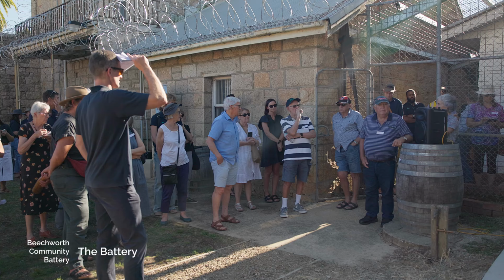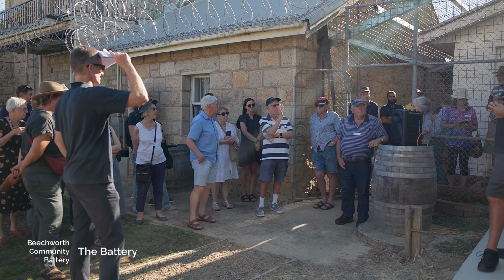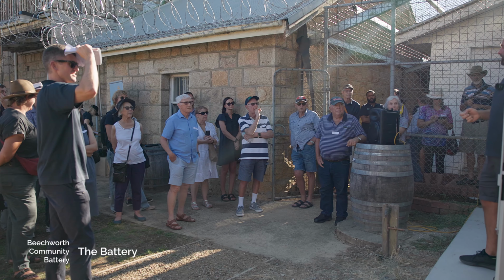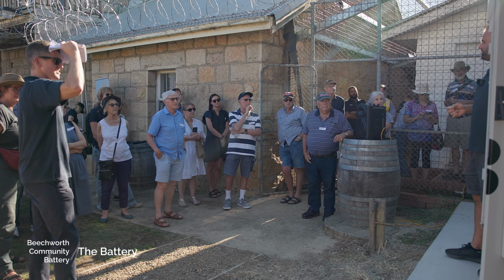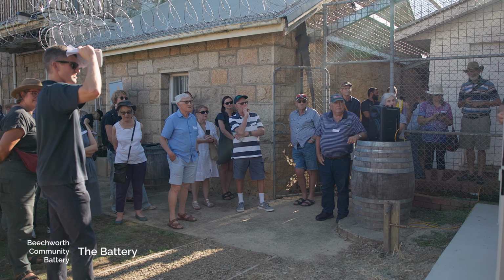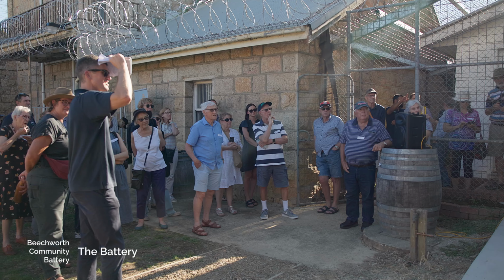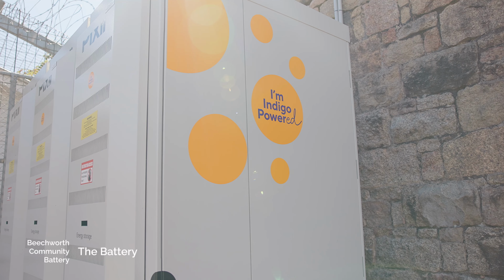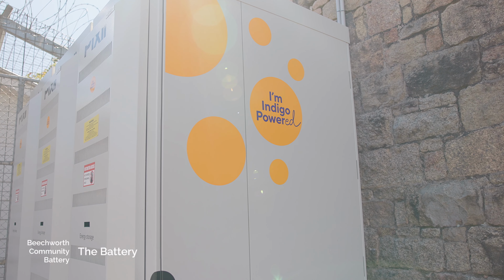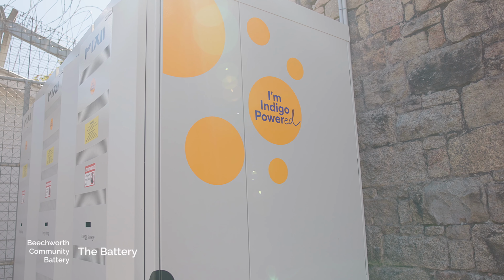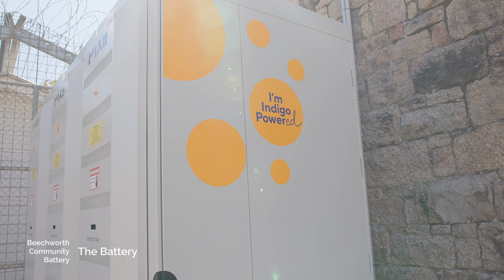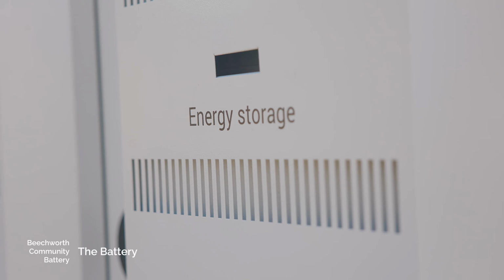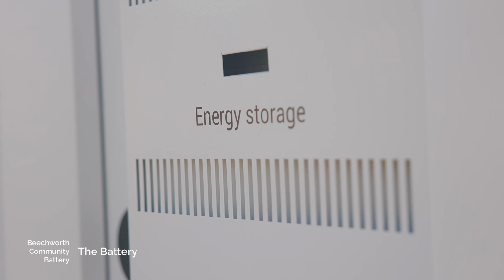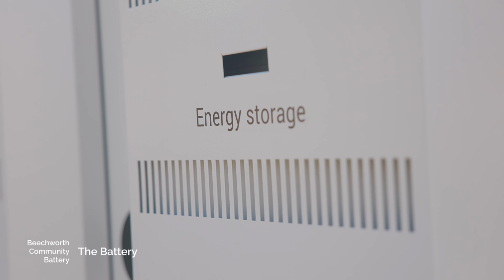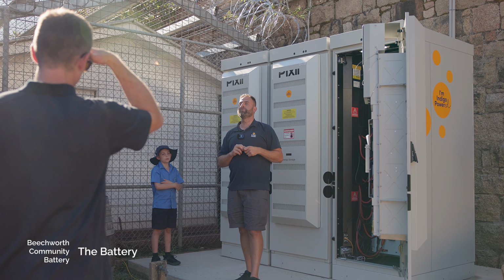With your batteries and inverters, what's your cooling mechanism? That's an air conditioner - a DC air conditioner that connects directly to the batteries. The inverters also have fans, so this is a controlled environment, about 21 degrees. If the grid goes down, that aircon still works because it's DC coupled directly to the batteries, and those cooling fans pump air through the inverters and cycle it back through the bottom here.